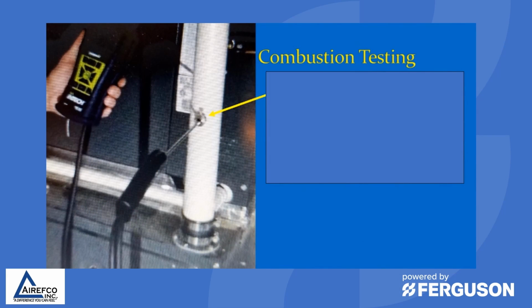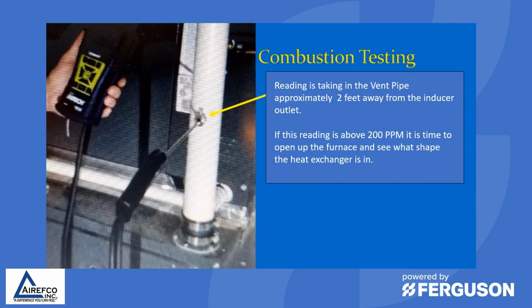Whenever a technician calls in and is working on a gas furnace where he suspects a bad heat exchanger, they are reluctant to open the furnace up, as that's a major operation to try to check the heat exchanger. So by doing a combustion test, we can try to determine whether we need to open the furnace up for further examination. Many technicians are reluctant to do this also, as it requires drilling a hole in the vent pipe about 2 feet away from the inducer motor to take the reading. If this reading is above 200 parts per million, it's time to open up the furnace and see what shape the heat exchanger is in.